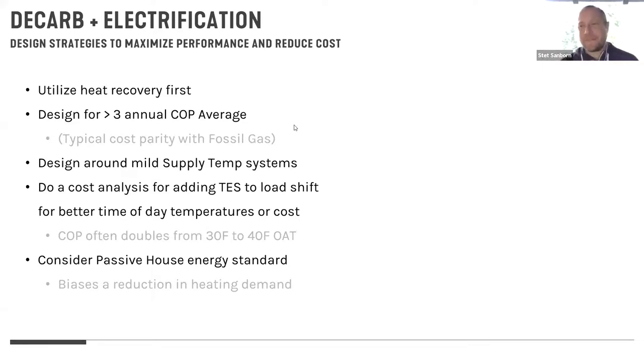So I've pulled together my top list of strategies when I'm looking at either new construction or retrofits, but mostly new construction, when I'm trying to look at a project for decarb or electrification. And they aren't necessarily in order, but they're kind of in order. The first one is, by all means, find ways to use heat recovery. And ideally not just a runaround loop, because in your climate, you guys would see more benefit than we do. But if we put a heat runaround loop on our exhaust air and our inlet air, our delta Ts just aren't amazing.